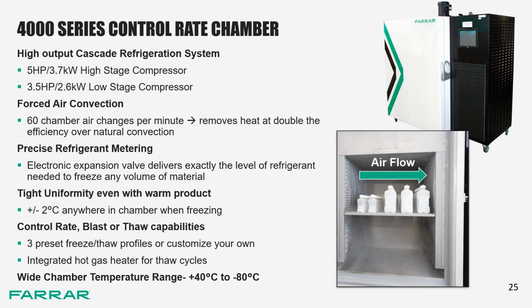So what this all does is it produces tight uniformity within the chamber. In an empty chamber when running, it's about 0.1 degrees Celsius anywhere in the chamber. When you add a significant heat load, such as a load of warm product, it may ramp up to about plus or minus 2 degrees, especially around that warm product as it's cooling, and down to minus 80.